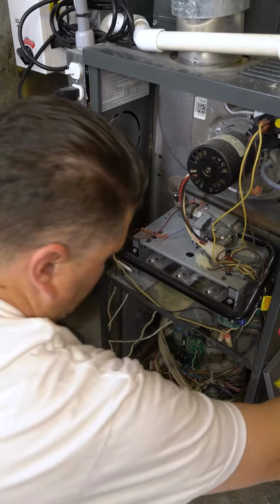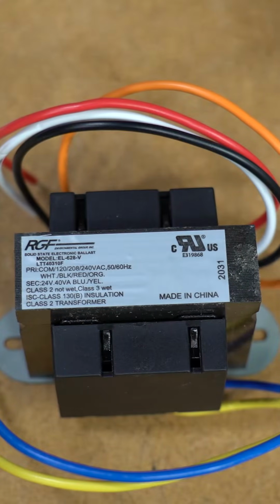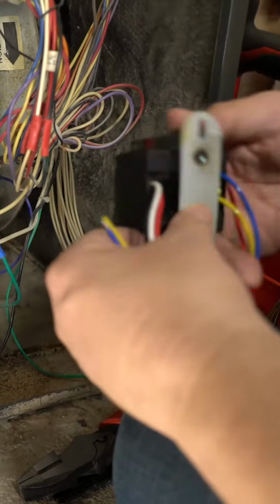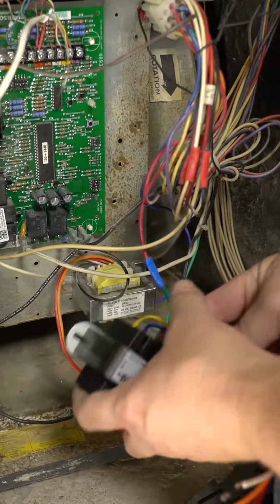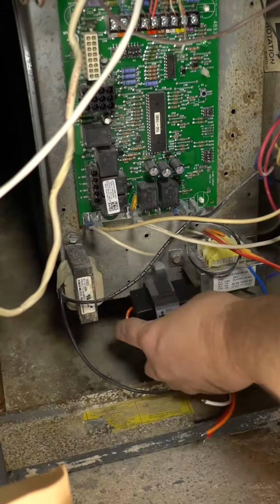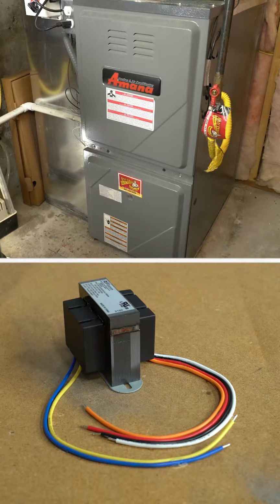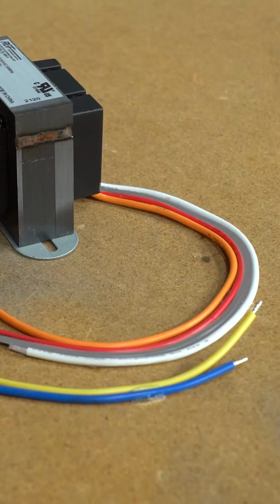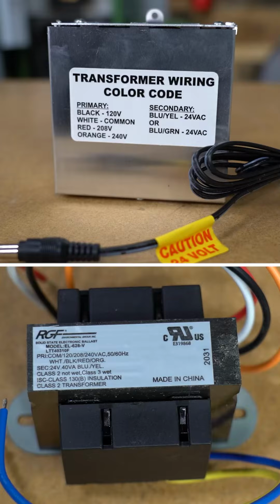The Reme Halo must be installed using the supplied transformer. I've got enough room inside the furnace to mount this transformer next to the circuit board and the other transformers. This is a standard 120 volt furnace, so I'll be using the black and white wires on the high voltage side of the transformer. If your furnace is a different voltage, adjust how you wire the transformer accordingly. Refer to the wiring diagram on the transformer if you aren't sure.